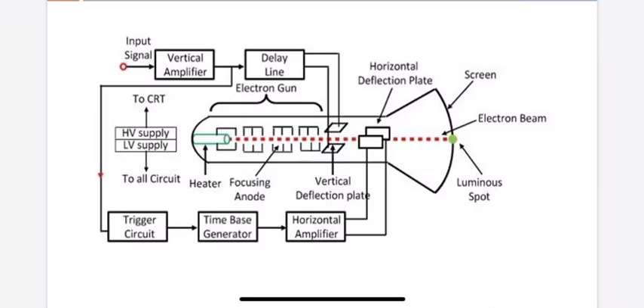Finally, the power supply consists of two blocks: high voltage supply and low voltage supply. The high voltage supply is used to power the electrodes of the CRT (cathode ray tube). The low voltage supply is used to power the electronic circuits such as the time-base circuits and amplifier circuits.